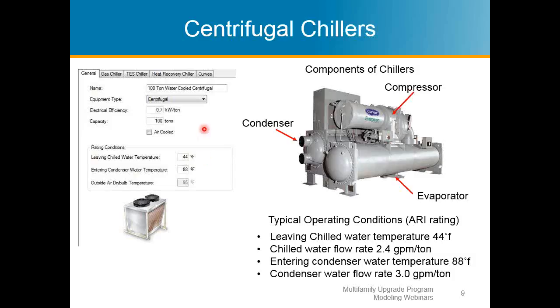Efficiencies for chillers are typically given in kilowatts per ton. So you're inputting that information in here for your electrical efficiency, kilowatt per ton. You have your capacity. Again, these are very large systems, so they can handle a lot of indoor units, and to size your chiller or your central plant, you need to know what your total load is and what your tonnage is to offset and satisfy the load.